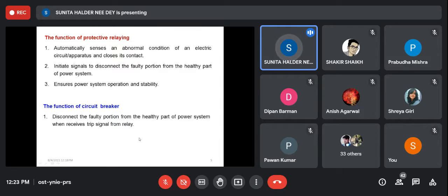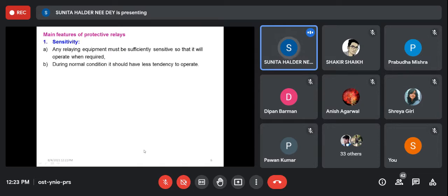So what is the function of protective relaying and what is the function of circuit breaker? I have already discussed and pointed out the topics here. Now, what should be the main feature of a relay? The relay should be sensitive. It should sense whatever the current is. Otherwise, it cannot protect any system. During normal condition, it should not operate. We should set the relay setting in such a way that at normal condition it should not operate, and at every abnormal condition it should operate. That means, for the example of 500 ampere normal current, ideally for 500.1 ampere it should operate, and for 500 ampere it should not operate.